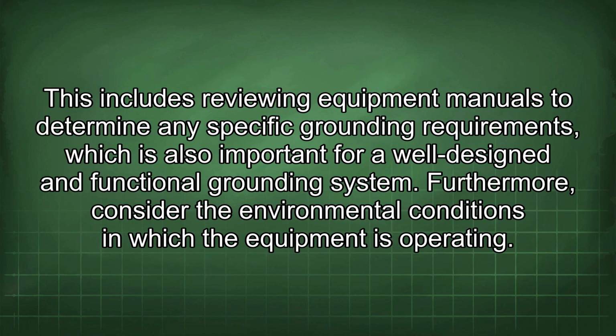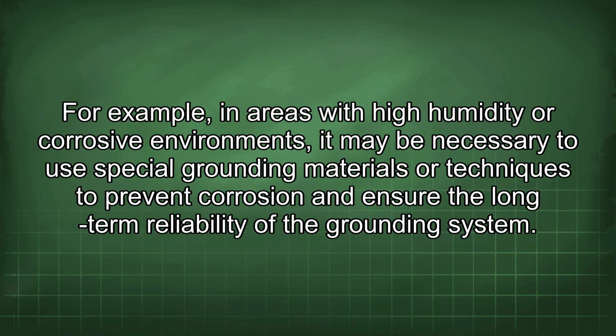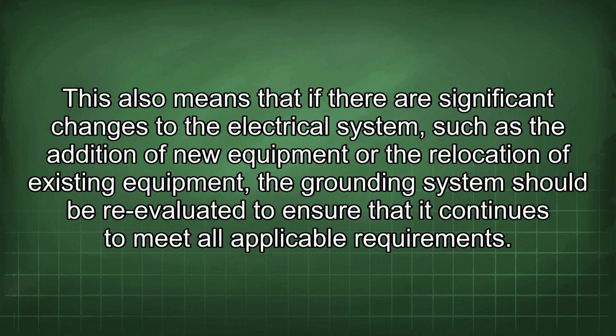This includes reviewing equipment manuals to determine any specific grounding requirements, which is also important for a well-designed and functional grounding system. Furthermore, consider the environmental conditions in which the equipment is operating. For example, in areas with high humidity or corrosive environments, it may be necessary to use special grounding materials or techniques to prevent corrosion and ensure the long-term reliability of the grounding system.